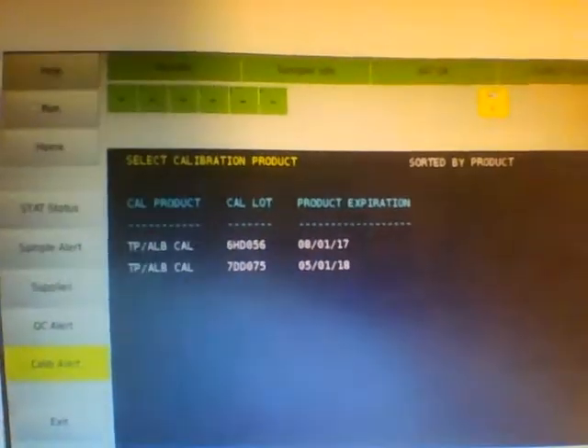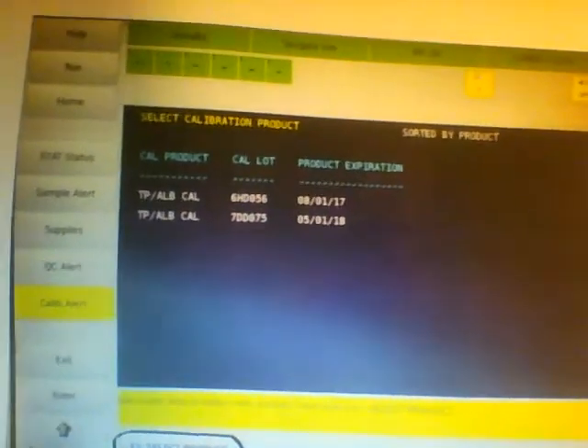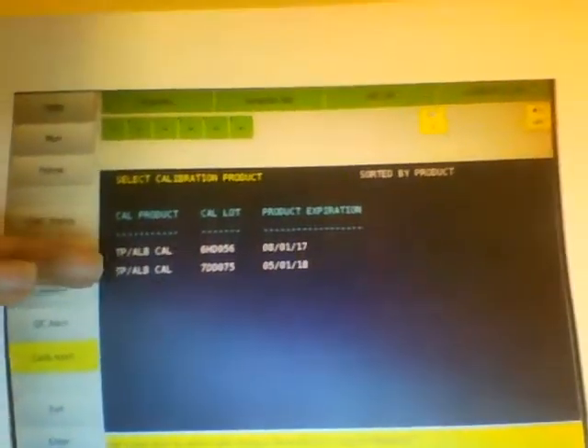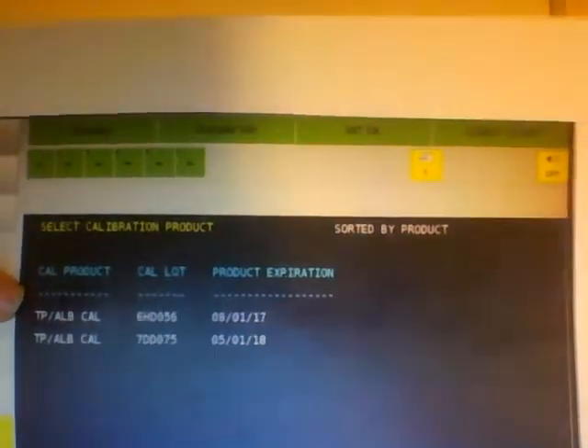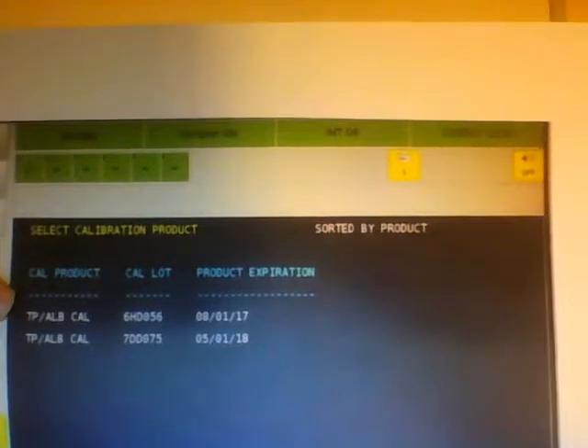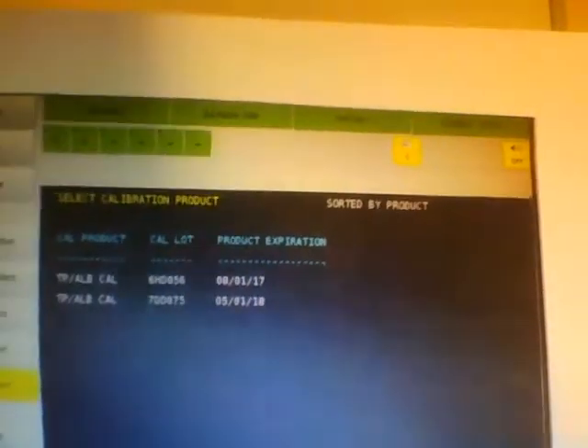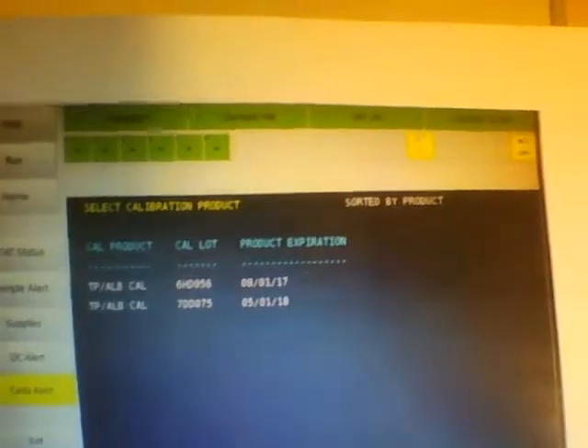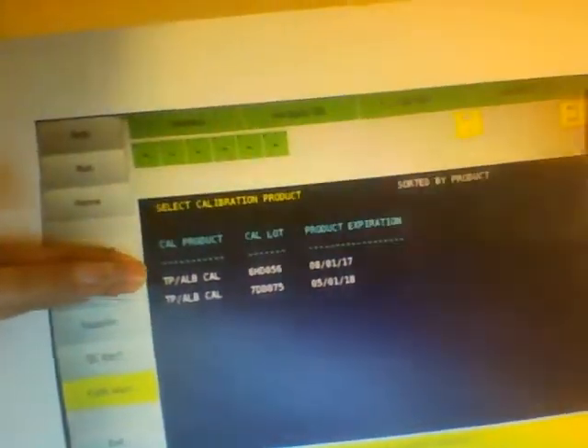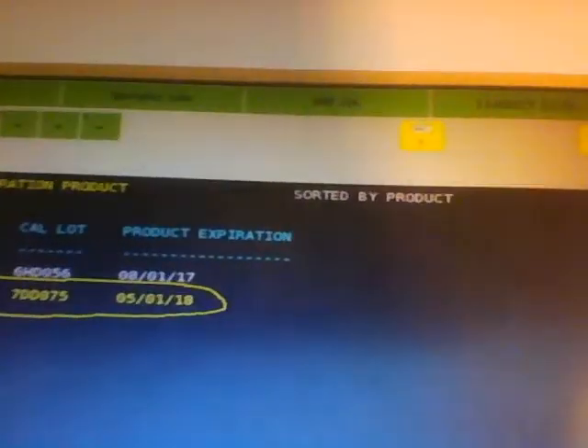So next, let's push a key. Let's say you pushed ALB. You're going to get to this screen, and it's going to say F1 select product, and it's going to have your calibrators up. You're just going to match up the lot of the calibrator you want to the lot of the calibrator that's right here. Once you choose the calibrator that you want, you push F1, select product, and it's going to highlight your product in yellow.